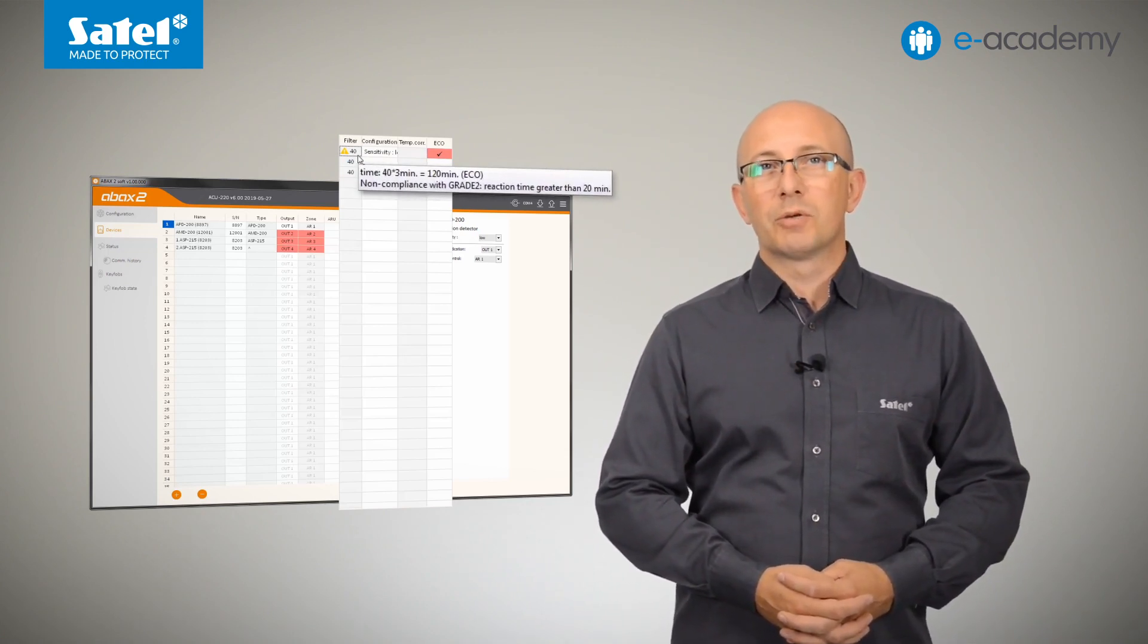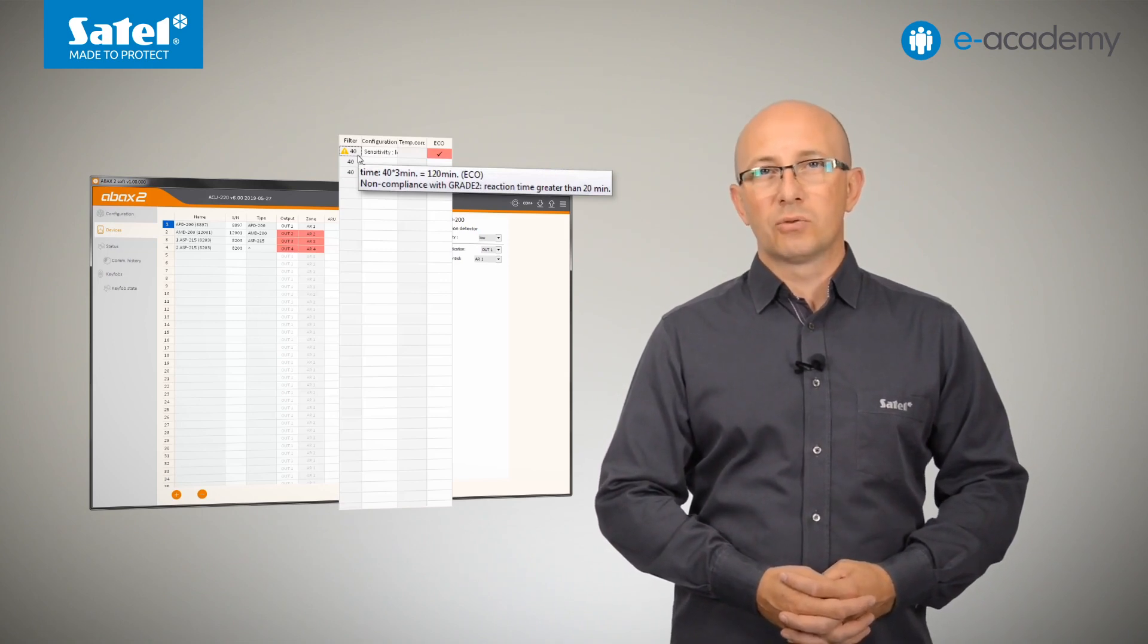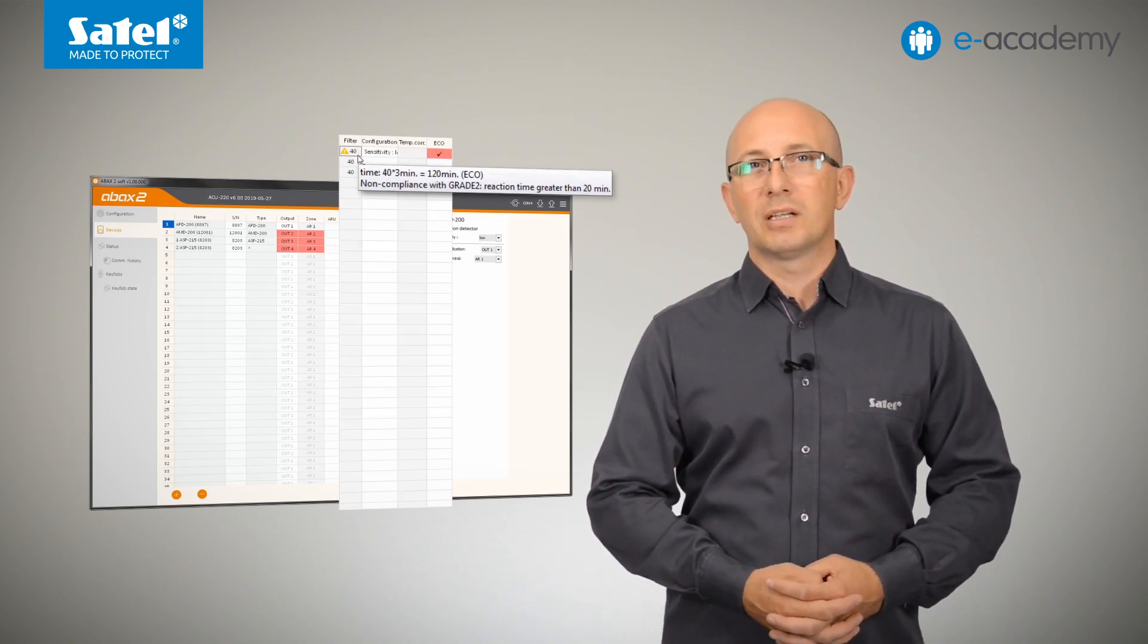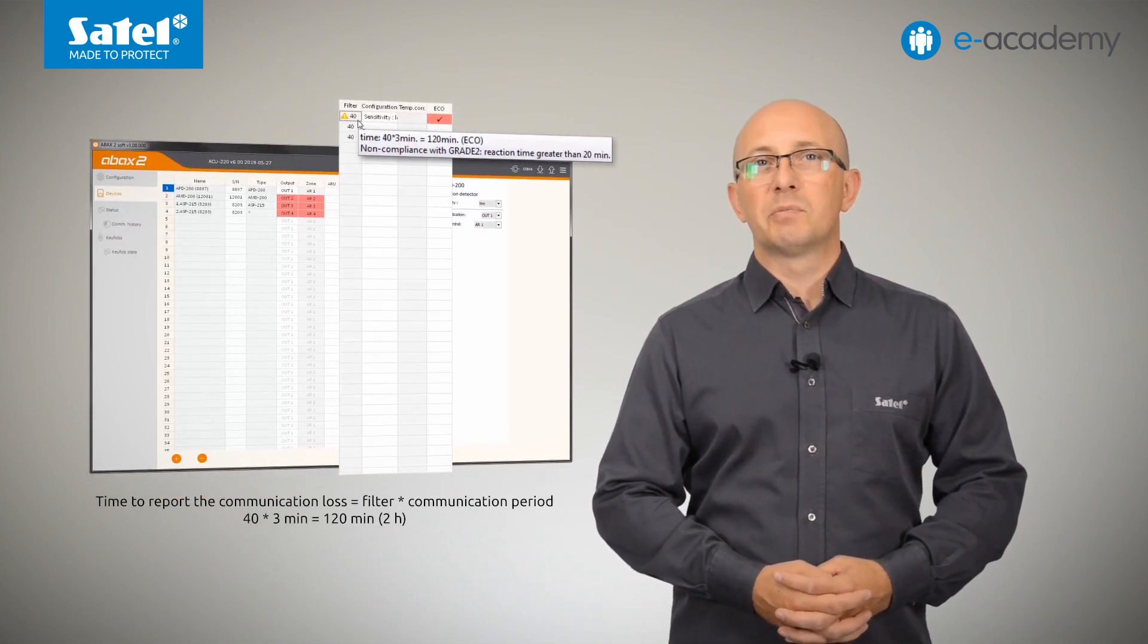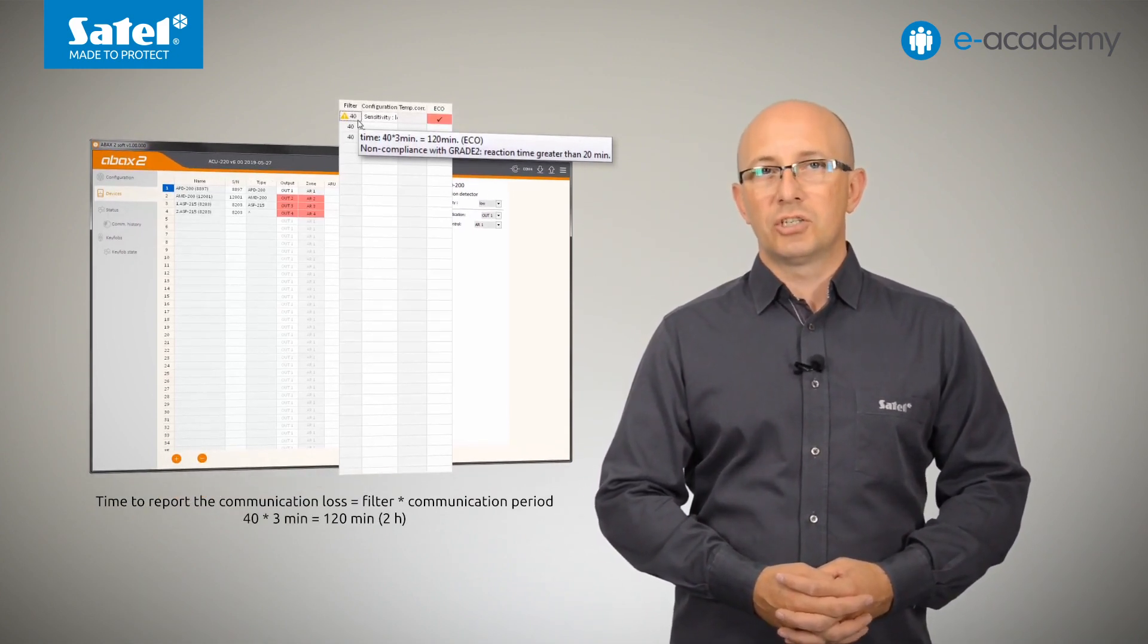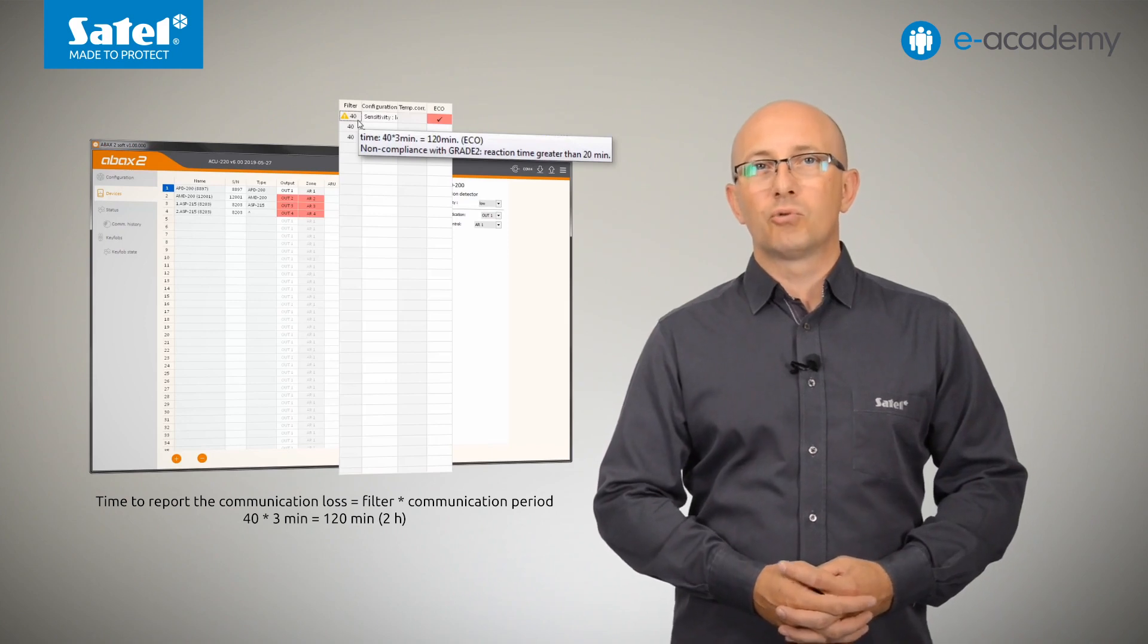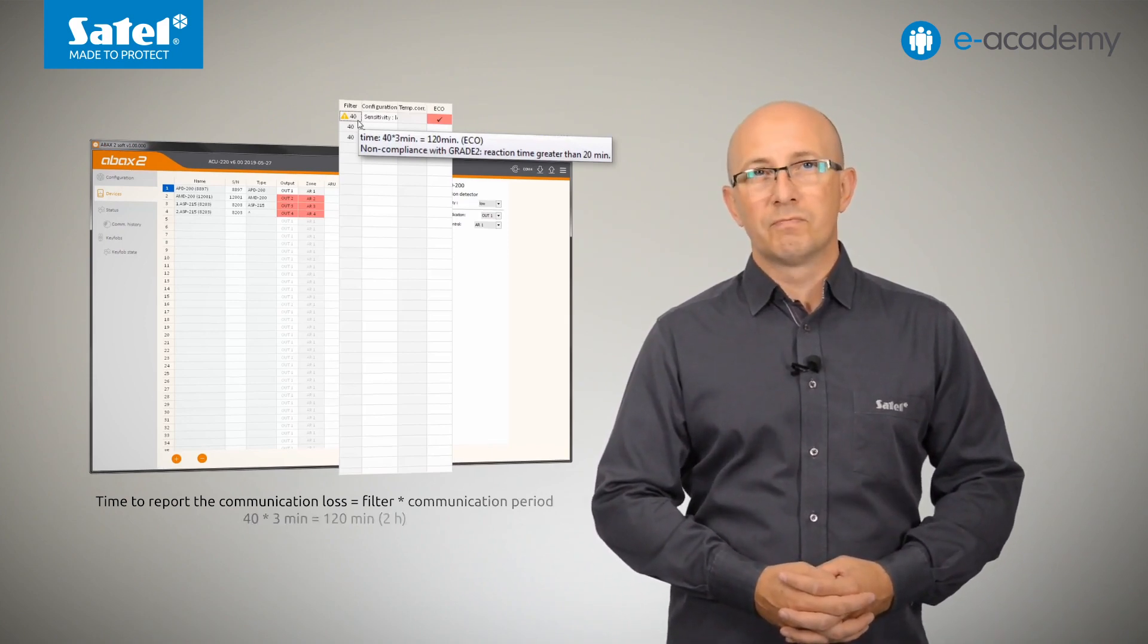Remember, however, that this will also prolong the time that must elapse before communication loss is reported. In such a case, if you leave the default value, that is 40, in the filter field, a possible loss of communication with the device will only be reported after 2 hours.